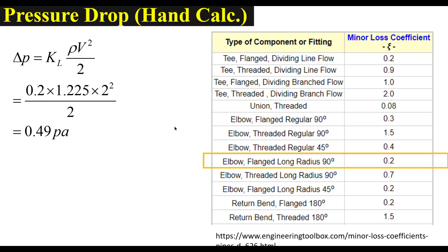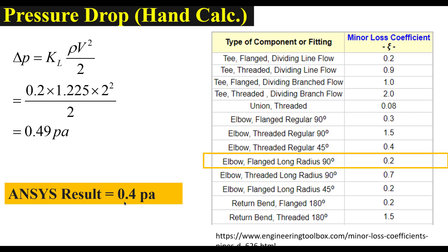Now we will do some hand calculation to validate our ANSYS solution. We have the formula for pressure drop in a pipe bend, where KL is the loss coefficient. This loss coefficient is equal to 0.2 for a 90 degree long radius pipe elbow. By hand calculation, the pressure drop value is equal to 0.49 Pascal, and from ANSYS we obtained a result of 0.4 Pascal, which is very close to our hand calculation. So our solution is validated. Thank you for watching this video. In my coming videos I will present more examples to calculate minor losses in piping systems.